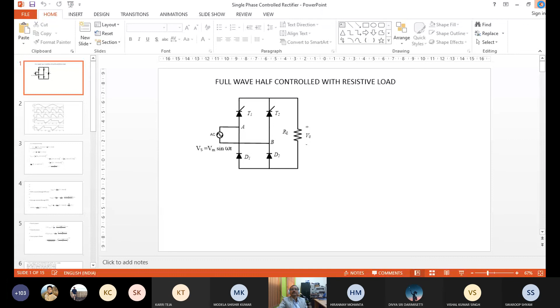Sharing of voltage and blocking of voltage are both the same? Where is sharing of voltage? Voltage is not shared. Current is shared. In the series connection, voltage is blocked, because it appears across a device, across a circuit. Voltage is across, and current is in series. Non-uniform current sharing happens in parallel operation. Unequal voltage distribution happens in series operation.